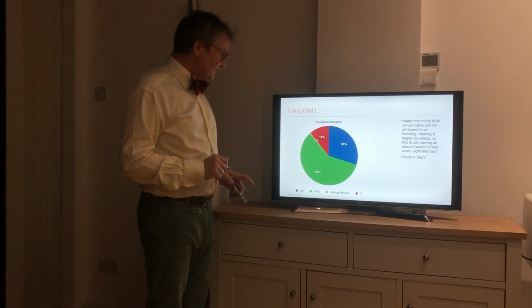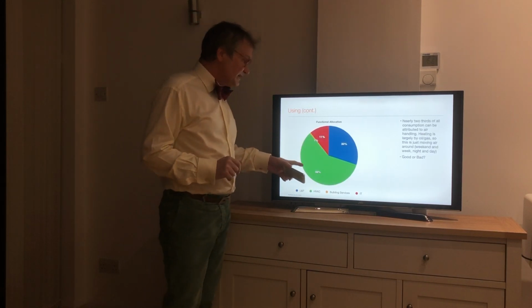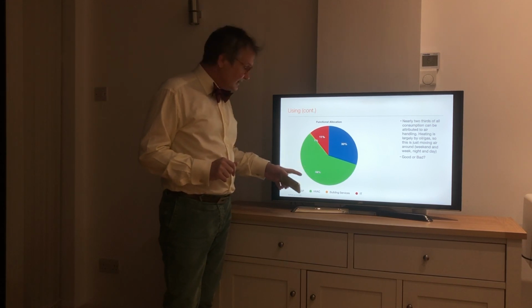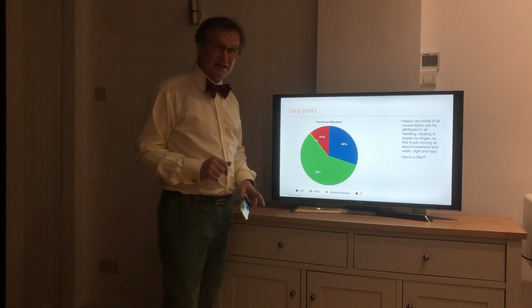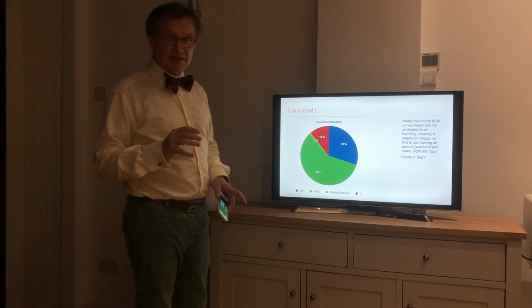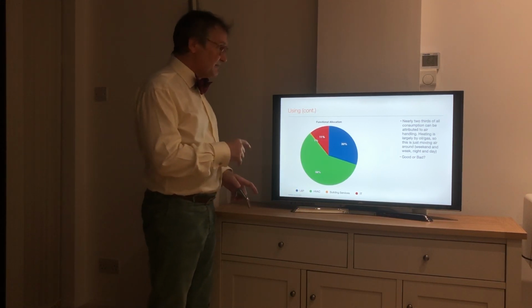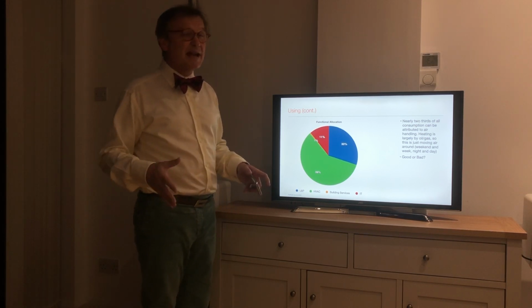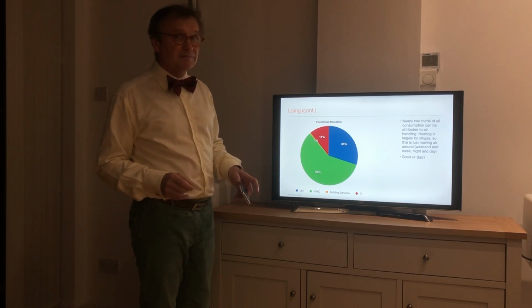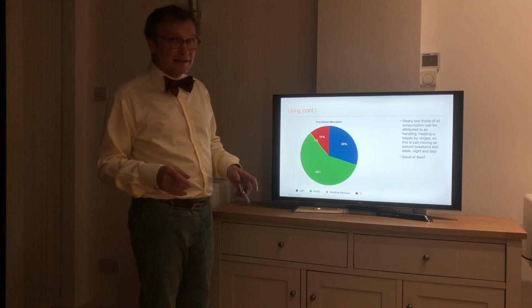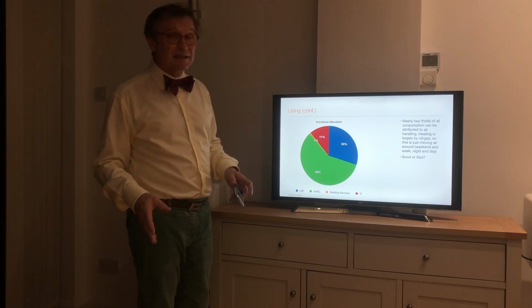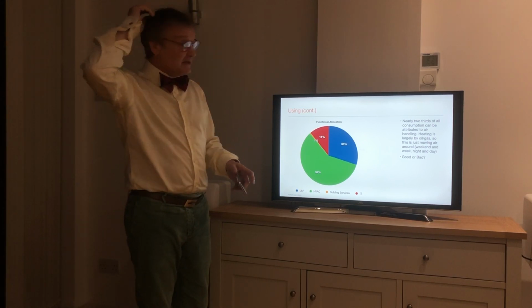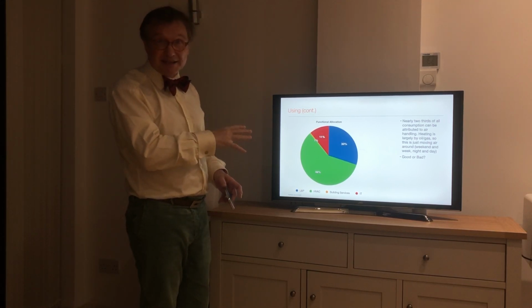This is the breakdown. You should immediately be drawn to the fact that nearly 2/3 of the power is involved in heating and ventilation. And that's pretty amazing when you think that the chemistry building is heated by gas in this particular case. So this is really just moving air around. And what's significant about it is also that you can't do anything about it. It's no good turning lights off or changing anything in your control. This is purely something down to estates in the building.